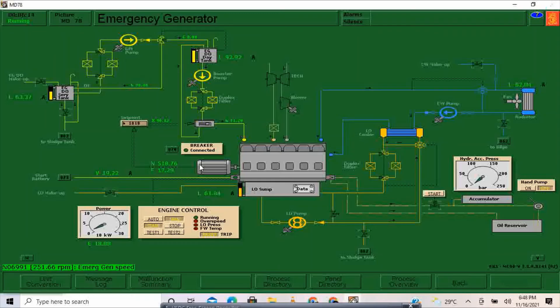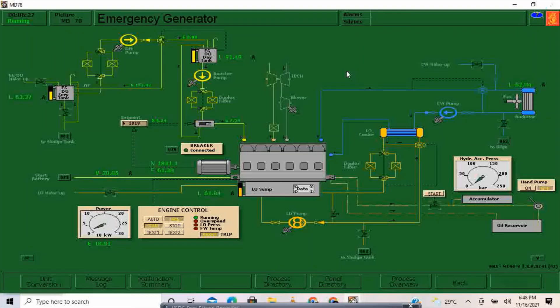There is already an increase in RPM. So far so good. We've already passed the exercise — we've done the topping up of diesel oil, lube oil, expansion tank, and we've rectified some malfunction alarms. We managed to test it hydraulically and everything was fine, and we've done a battery start.